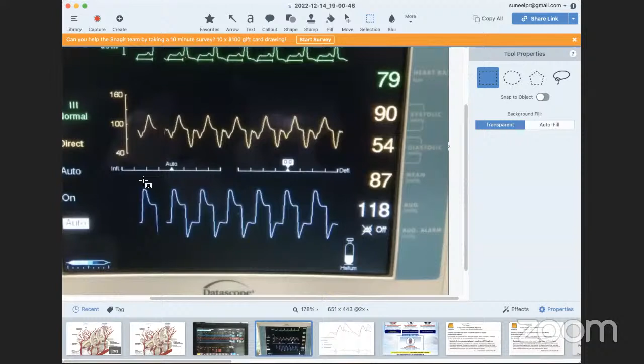Besides the trigger option, we do have something known as an IABP frequency ratio. That is 1:1, 1:2, and 1:3. So instead of augmenting every beat, we can reduce it to 1:2 augmentation and see for a couple of hours if the patient tolerates it, and then reduce it to 1:3. That is, every third beat is assisted by IABP. So this is one method of weaning, and the other thing is something known as augmentation.